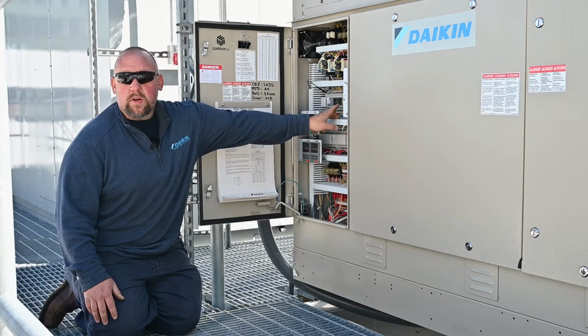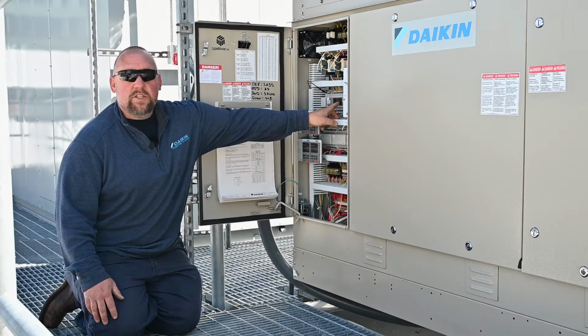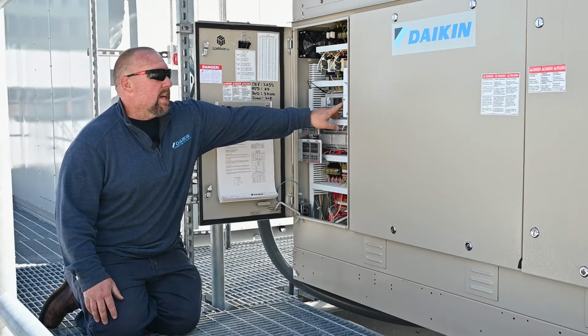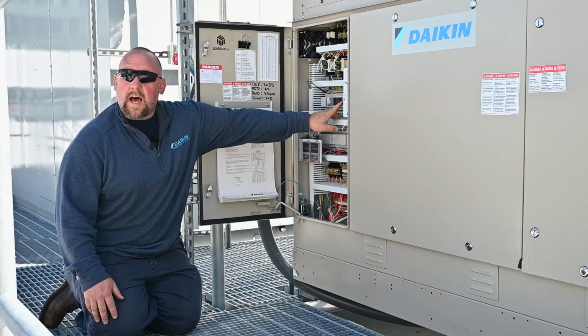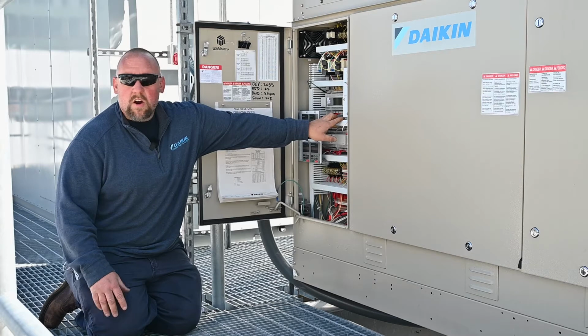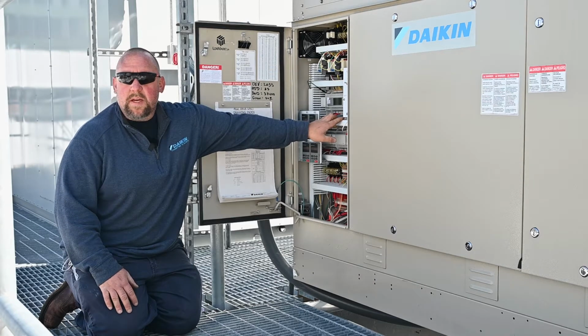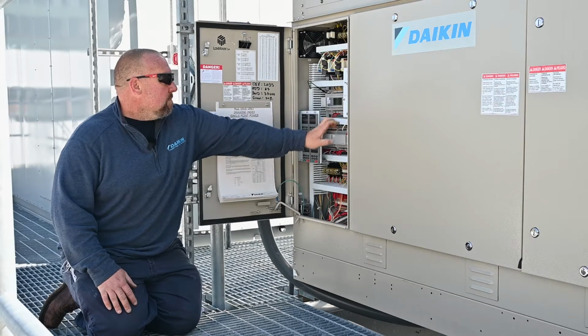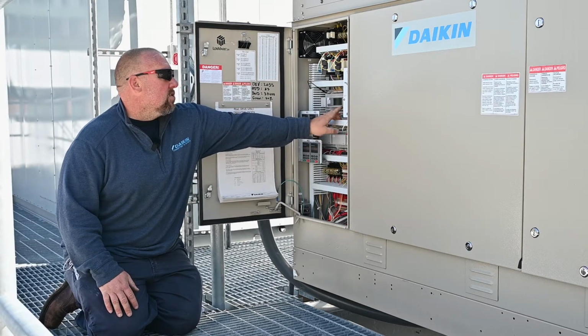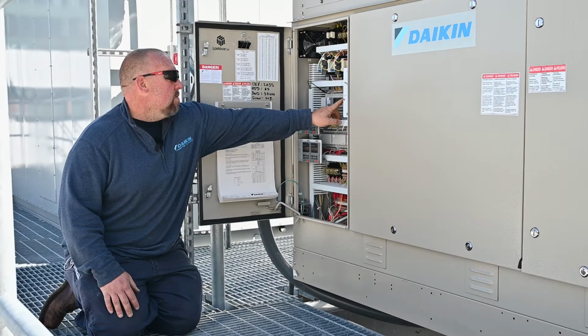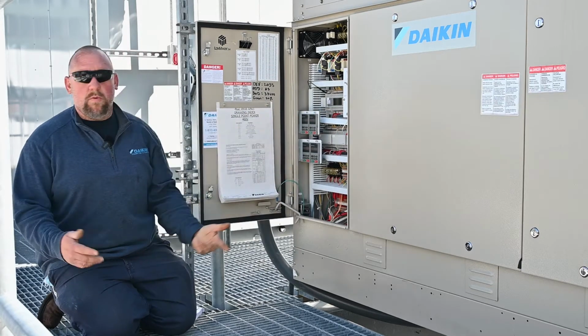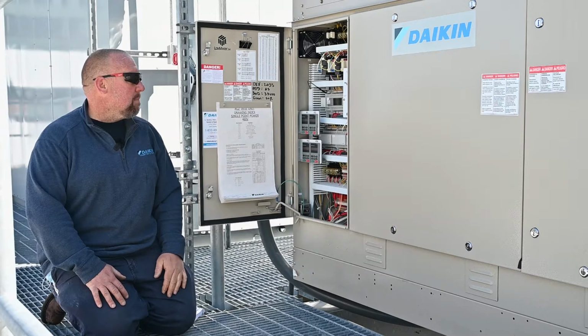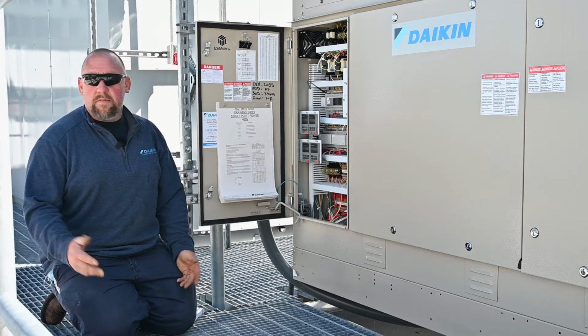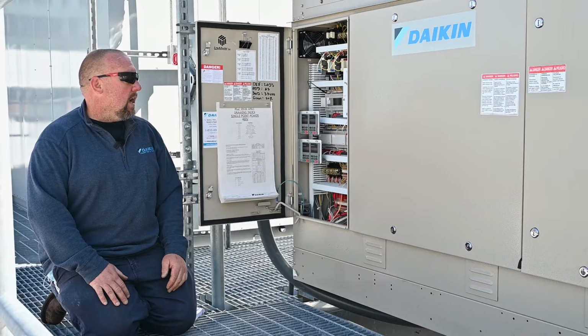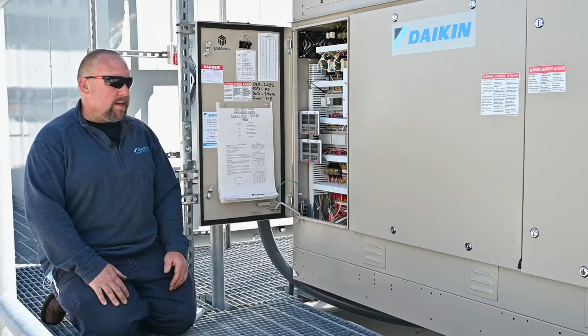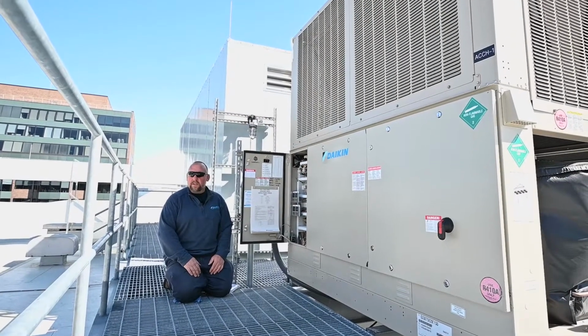If there was an alarm, you could clear it on this same page. Right next to it, it says alarm clear. You would click again, and you could scroll with this dial to alarm clear on, and it will clear anything that is able to be cleared. Anything else on here will show you your active set points, your leaving water temperatures, the percentage of what it's running right now.